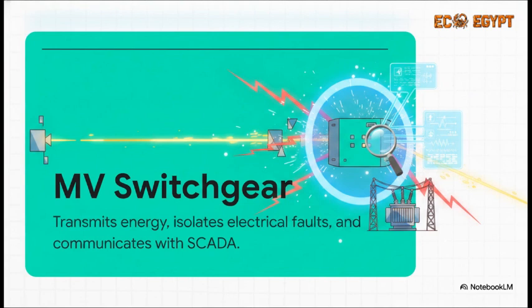To truly grasp the massive scale of a utility PV project, we absolutely have to understand the core mission of its medium voltage infrastructure. The MV switchgear is effectively the central nervous system of the whole PV plant. It is definitely not just some passive metal box humming in the desert. It's a dynamic, living system carrying out 3 absolutely critical missions simultaneously. First off, it transmits energy from the inverters all the way to the step-up transformers and the utility grid. Second, it acts as this massive shield, detecting and isolating electrical faults, like short circuits, before they can completely destroy your expensive transformers and inverters. And third, it provides control and monitoring by constantly communicating with the plant's SCADA system for remote operation.